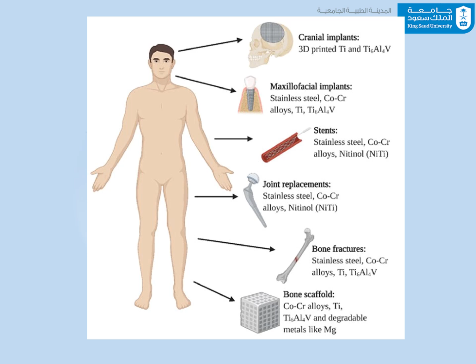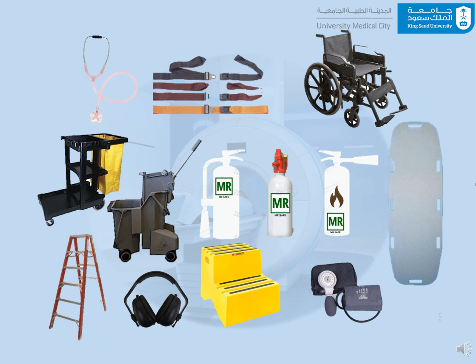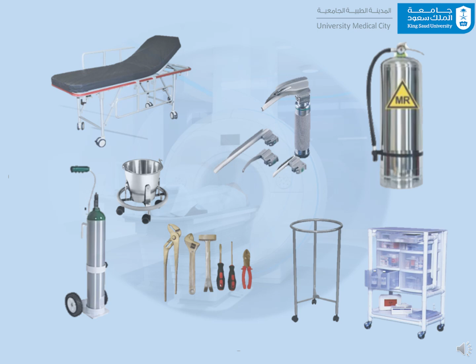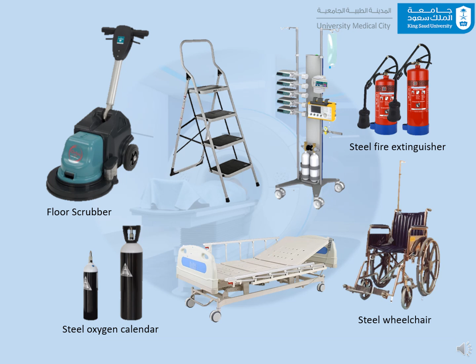There are three main classifications of objects in relation to the MRI examination room environment. MR safe: these are objects that pose no known hazards in any MRI setting. MR safe items include non-conducting, non-magnetic materials such as plastic. An object may be deemed MR safe based on scientifically grounded information, rather than solely relying on test data. MR conditional: the safety of these objects depends on the specific MRI environment. More testing and evaluation is required to determine their compatibility. MR unsafe: these are objects that are unsafe to bring into any MRI environment, as they present serious hazards.